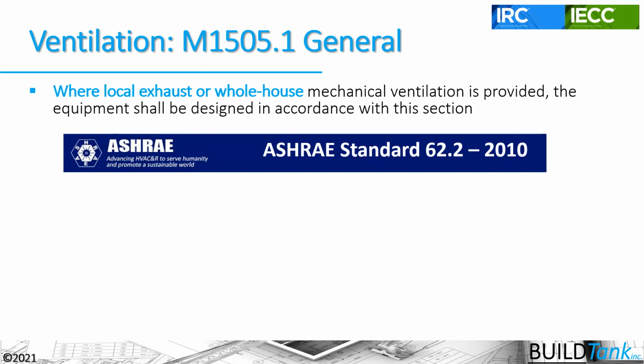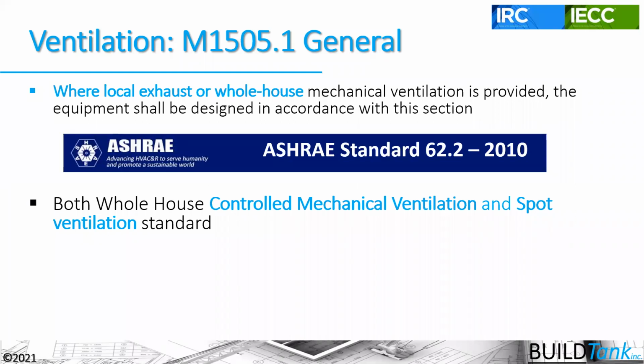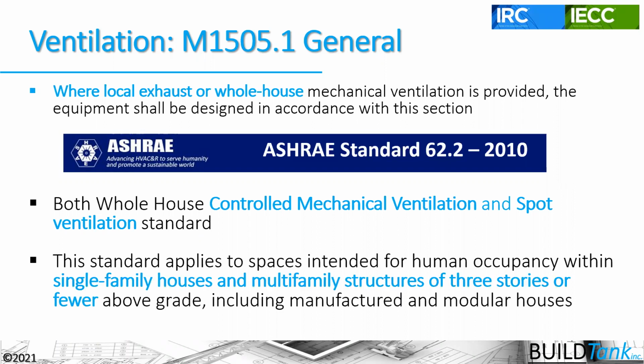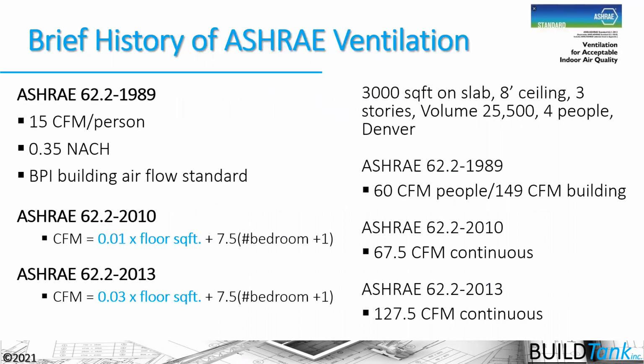And it does that because this standard deals with controlled mechanical ventilation and spot ventilation flow rates. It's also dealing specifically with the housing type that the IRC and the IECC are dealing with on the residential side. So just to give you an idea of the difference in these standards, the ASHRAE standard is a continuous maintenance standard, so it's changing roughly every 3 years. The ones that are most significant from a code perspective are the 1989 version, which introduced this 15 CFM per person and this 0.35 natural air changes rate. And so you might be familiar with that. This is where it comes from.